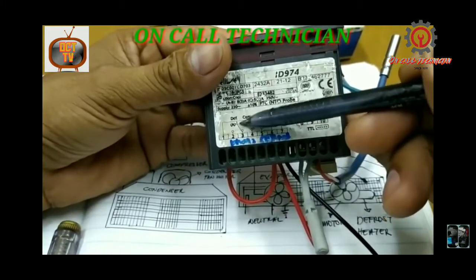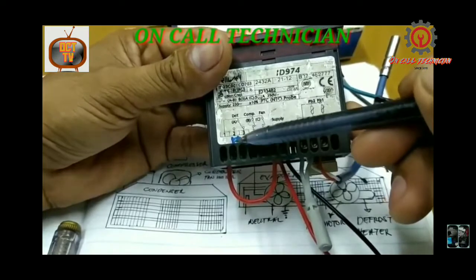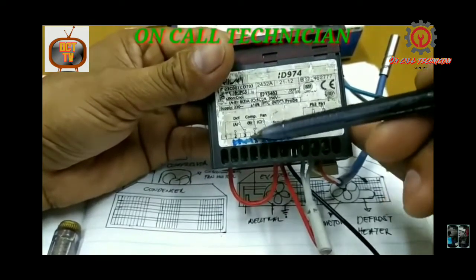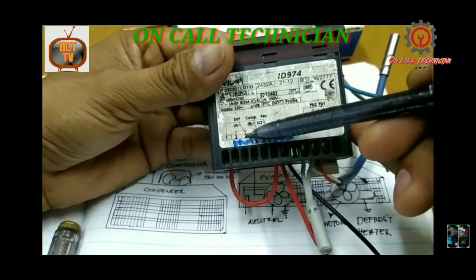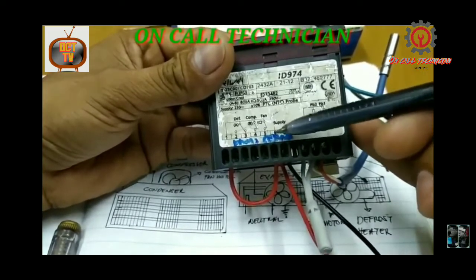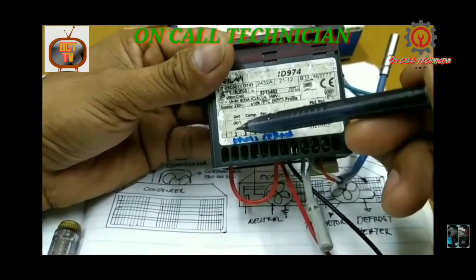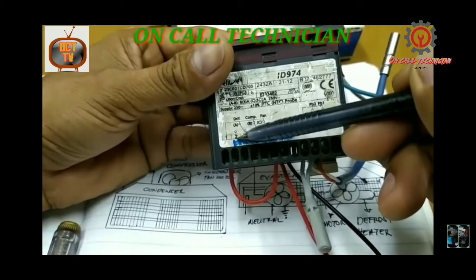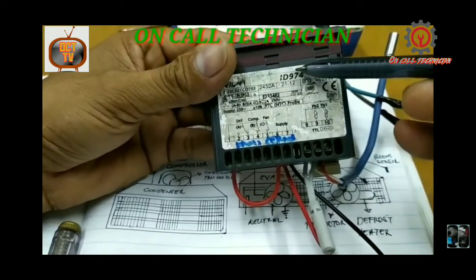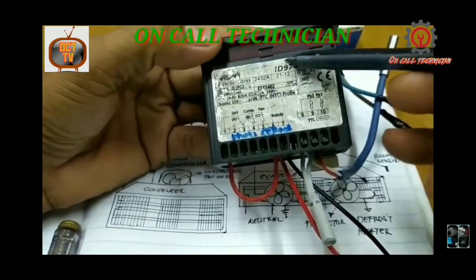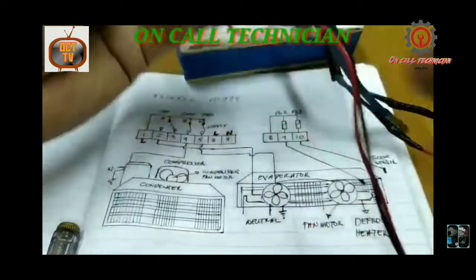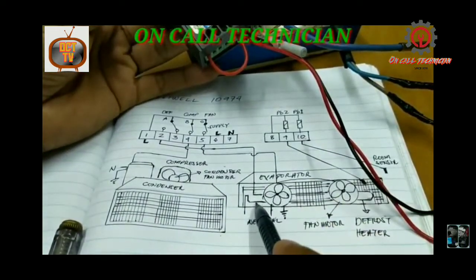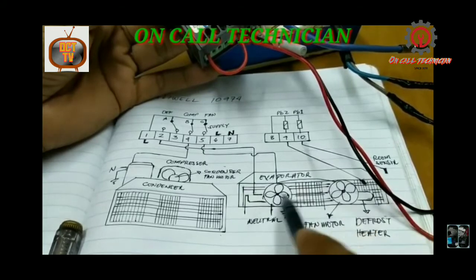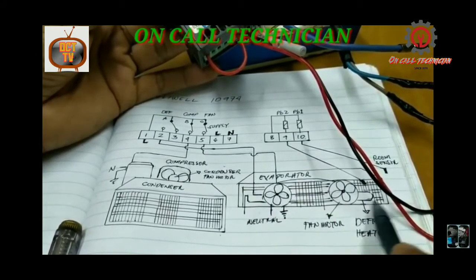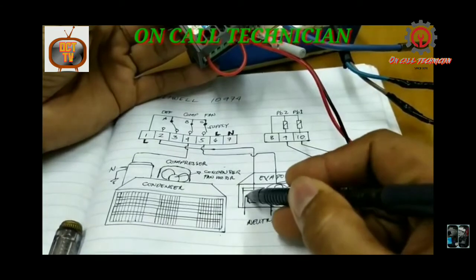Okay, so terminal number 3 is the compressor, and here number 2 is for the defrost. And 3 is the normally closed, and 2 is normally open. For example, if your output relay for the fan motor is defective, you can put it to terminal number 3, which is normally closed, so it will run. So that is a tip, guys.